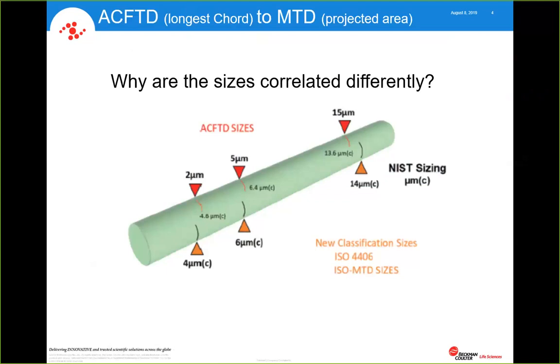You're saying today you have HRLD400. If you changed them to 100s and then calibrated, well, not calibrated with AC fine test dust, but calibrated with the standard, the ISO MTD, and then we were to go back and rerun an ACFTD calibration fluid using the NavAir recipe. You're saying there's an algorithm that should compensate for the new standard, if I understood you correctly. It doesn't compensate, but it does report out to the correct legacy sizes. Okay. Would that show equivalency that way?